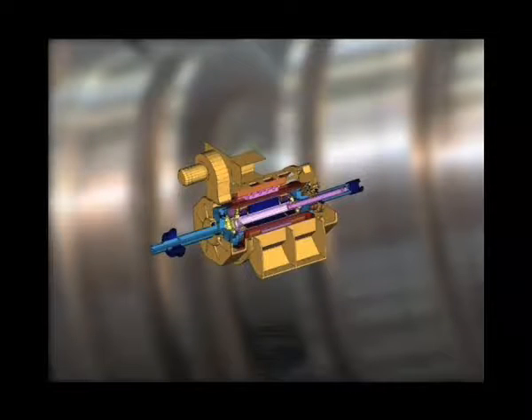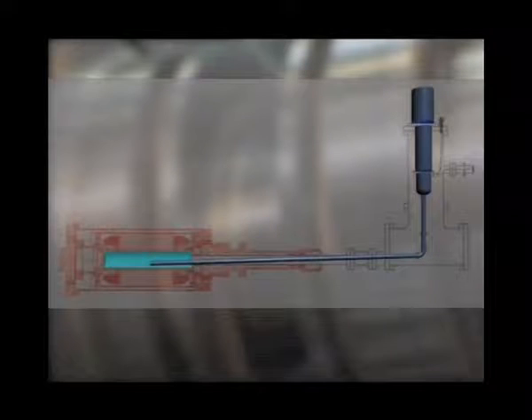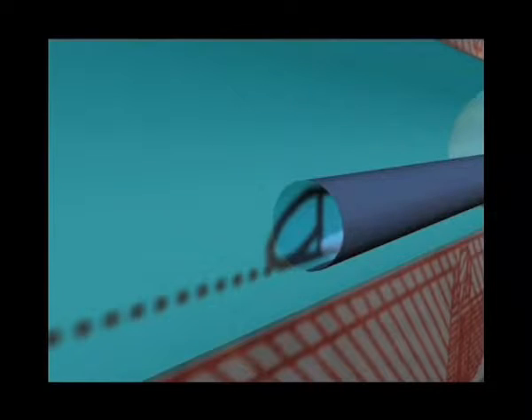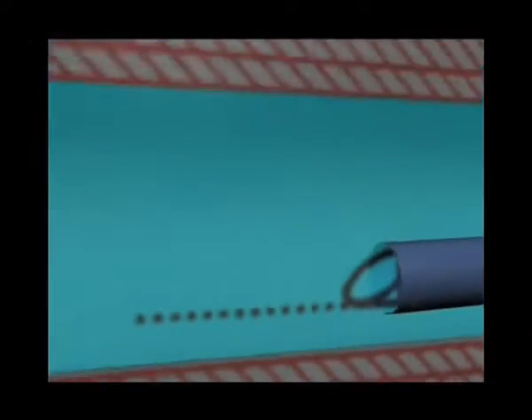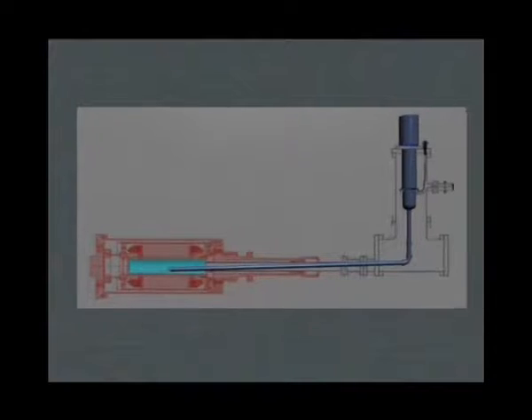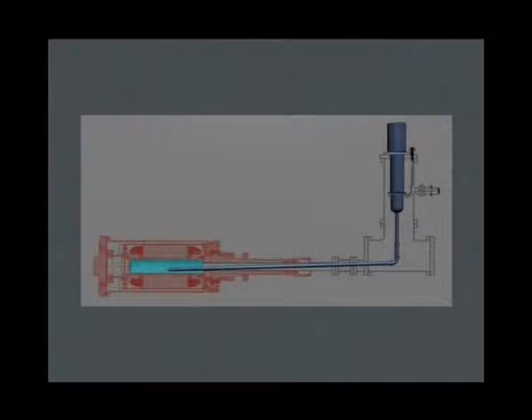A self-regulating cooling system is developed to cool the rotor to the operating temperature of about -250 degrees Celsius. A commercially available refrigerator cools the condenser. There, the working gas neon condenses and, driven by gravity, then runs through the cooling pipe into the rotor's interior. Here, it evaporates while cooling the rotor. The vapor returns to the condenser, where it is liquefied again. The cooling system is therefore a closed circuit, so the cooling system operates completely passively and requires little maintenance.